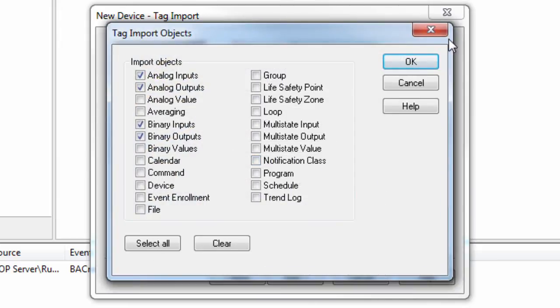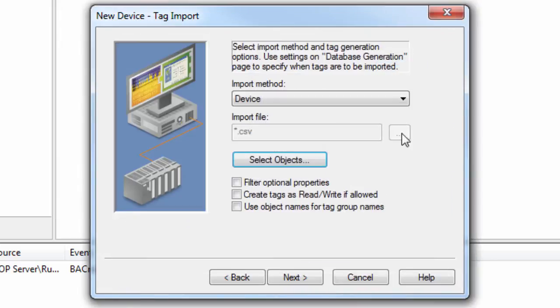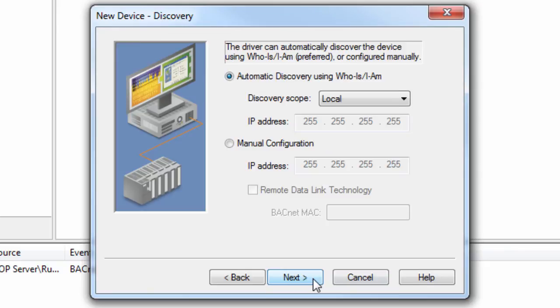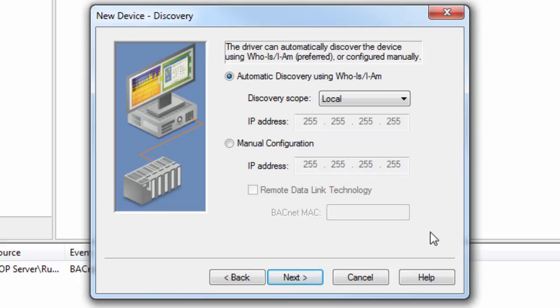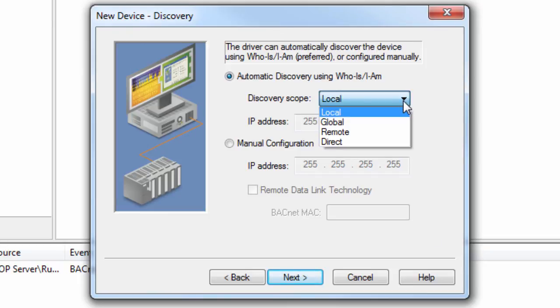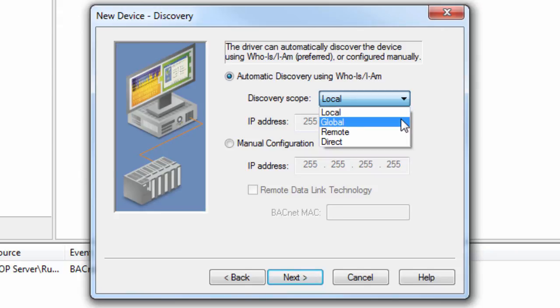Click Next to set the discovery settings. The driver can discover the device automatically or manually if the device does not support the I-Am and Who-Is services or broadcasting messages on the network is undesired. The discovery scope specifies whether the driver broadcasts Who-Is messages over the local Ethernet subnet, over the entire Ethernet network, remotely using the global broadcast IP, or directly using a specified IP address.